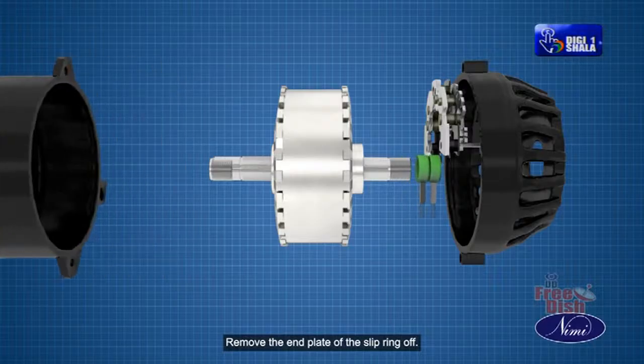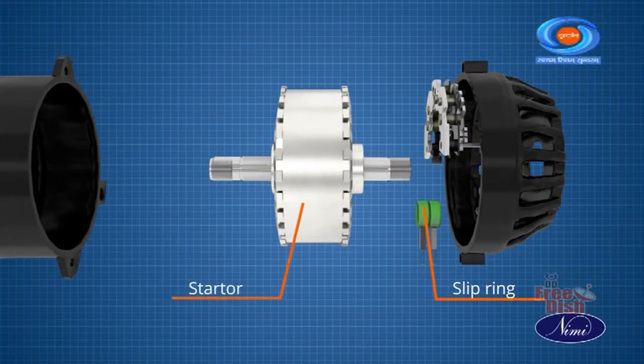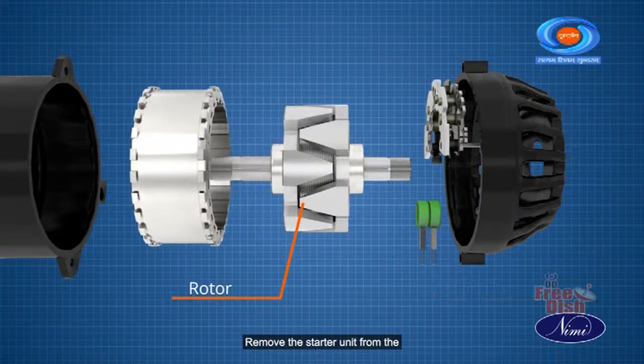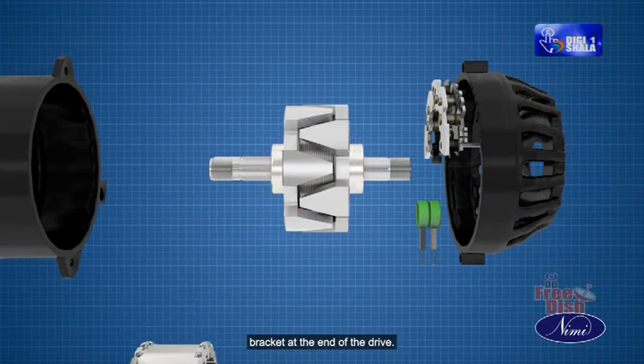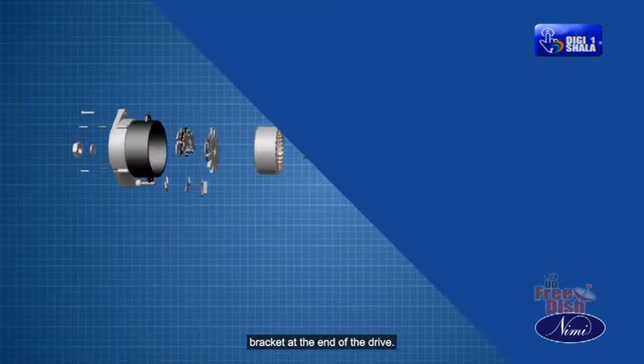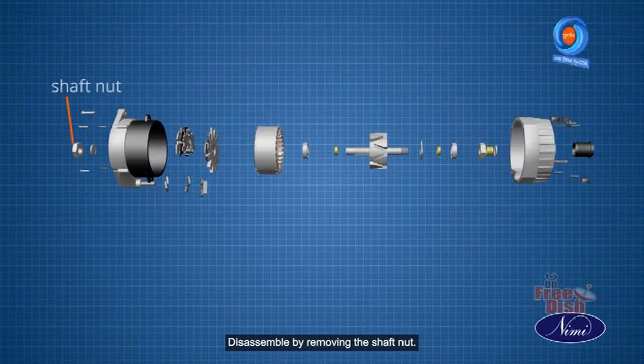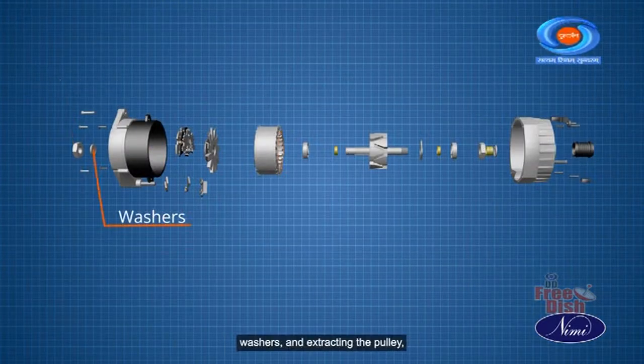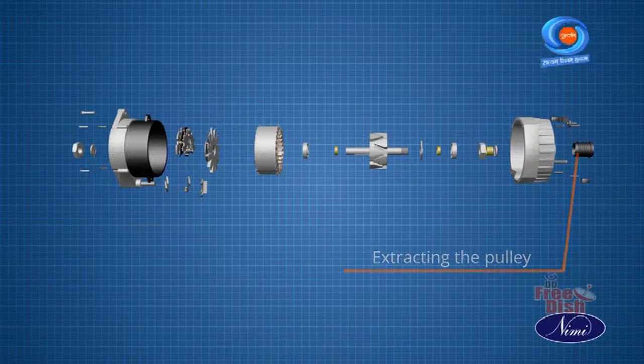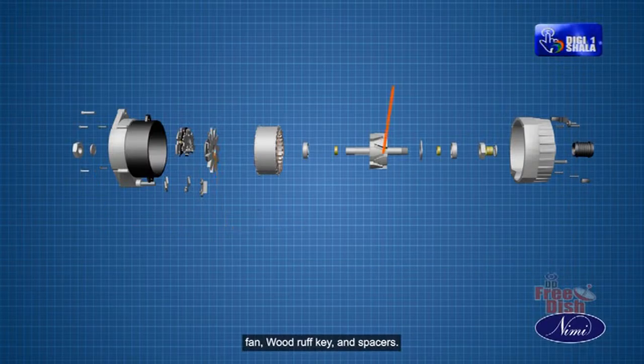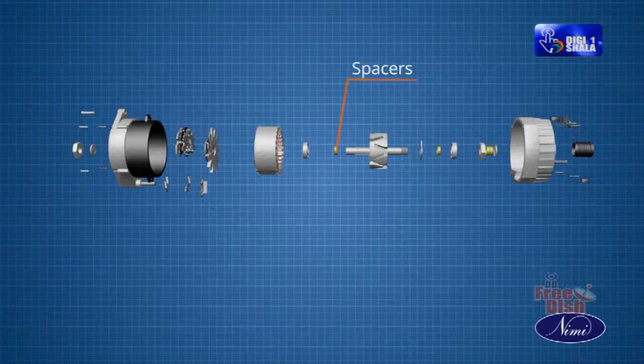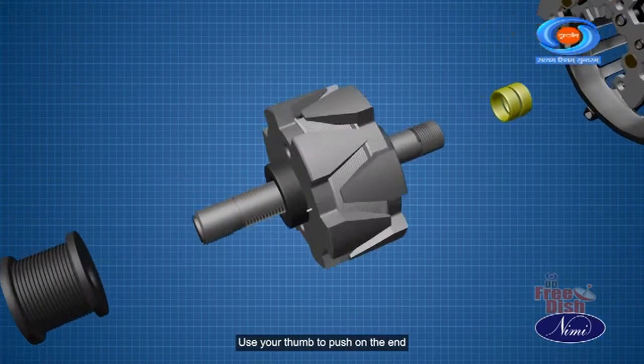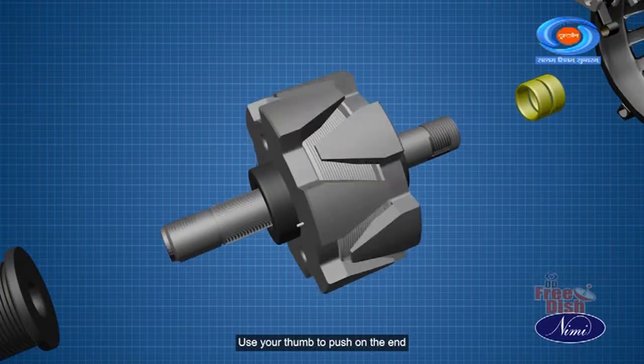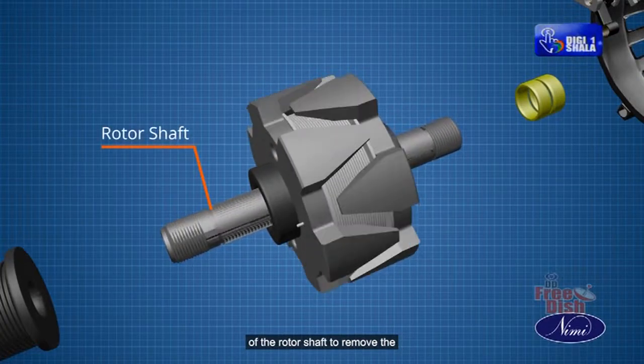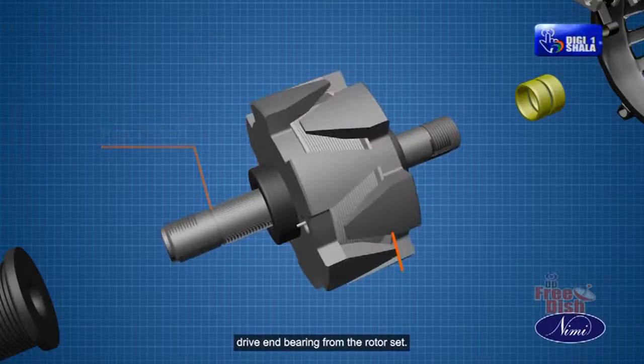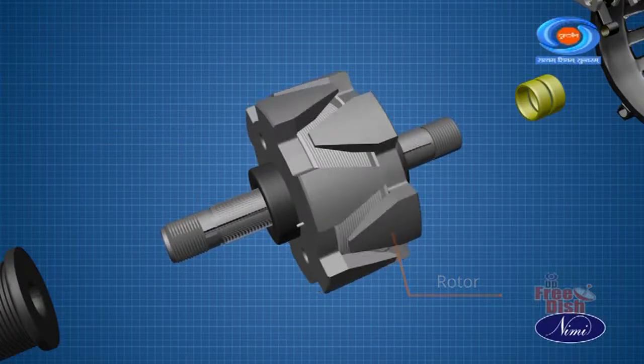Remove the end plate of the slip ring off. Remove the stator unit from the bracket at the drive end. Disassemble by removing the shaft nut, washers, and extracting the pulley, fan, woodruff key, and spacers. Use your thumb to push on the end of the rotor shaft to remove the drive end bearing from the rotor set.